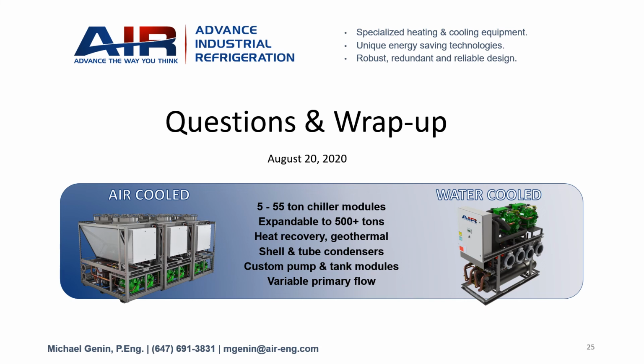What is the maximum hot water temperature? Well, it depends, like I alluded to earlier. Most chillers can produce at least 160 degrees if they are designed for heat recovery. In some instances, 170, 175 degrees. If you're using the correct refrigerant and if you're using a compressor type that is suitable for that amount of lift.